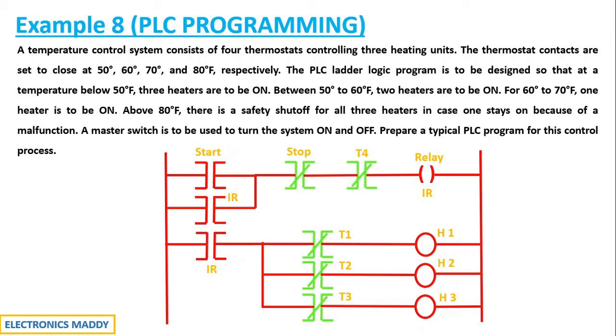If you carefully observe, I will be using a normally closed contact for T1, T2, T3, and T4. These are basically our thermostats — the sensors that are used. We have three heating units H1, H2, H3 connected to respective thermostats so that you can shut them off when they're not needed. I'm using a normally closed contact because if they're energized, they act as an open circuit and shut down the process for the respective heaters.